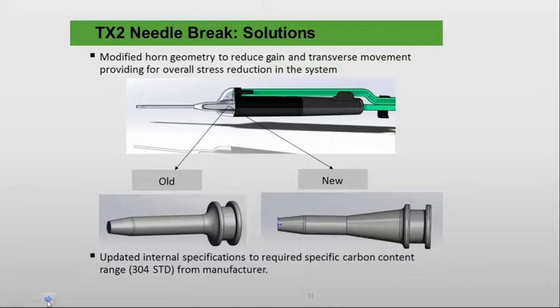We recognized it relatively early, within 3 or 4 or 5 months, and we posited a number of potential solutions, and I won't bore you with that, but we worked on it diligently for over a year. And fortunately, we finally did come up with the solution, which was a combination of 3 things. What you see on the slide right now is a design change, and all you really need to know is you see the old tapering of the device at the probe insertion into the component that is connected to the crystalline feature of the handpiece.